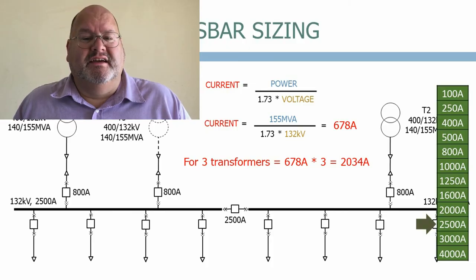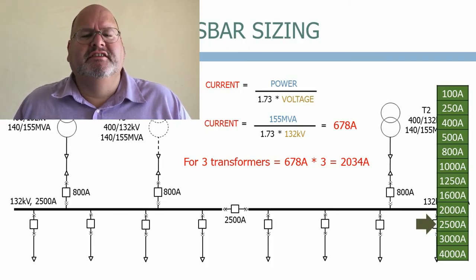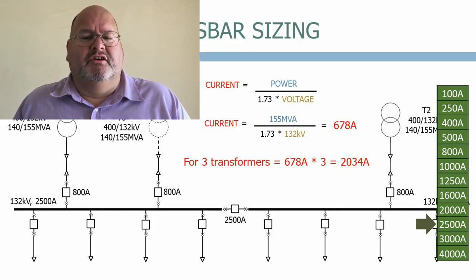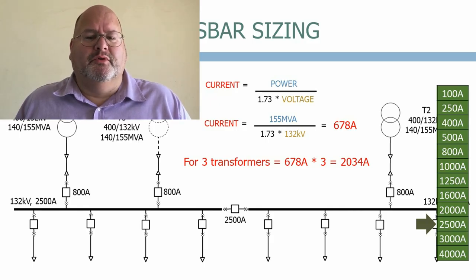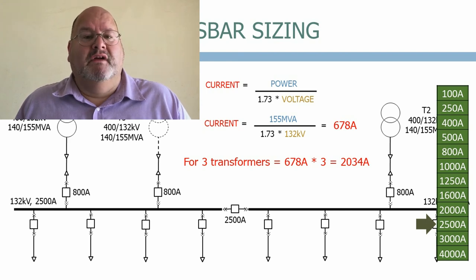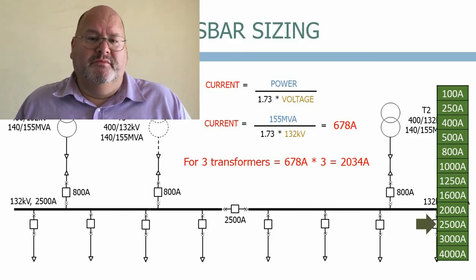Very often you will see designs where the incomers and busbar sections have the same rating. This is done as the purchase cost of similar sized circuit breakers can be minimal, and it also avoids having multiple circuit breaker ratings on the same switchboard. This keeps the cost of spares down and allows circuit breakers to be switched around between circuits when one of them fails.